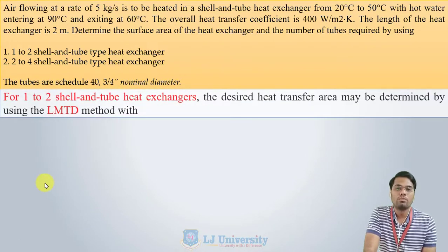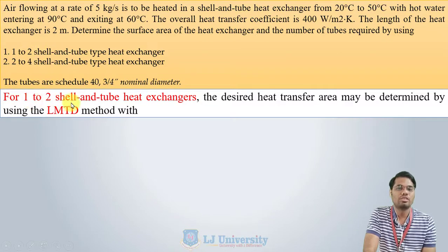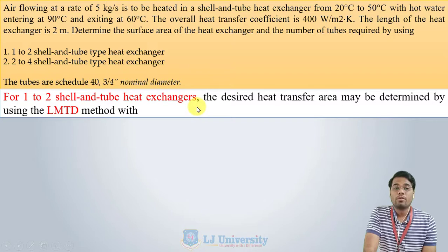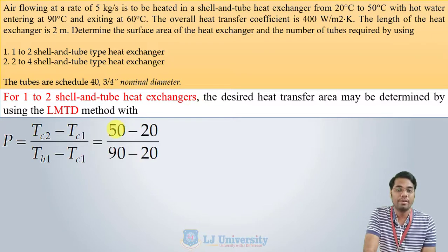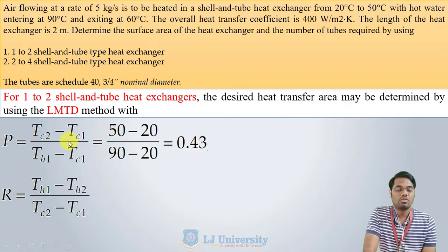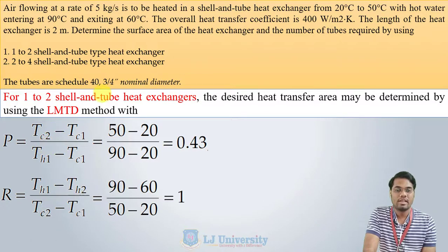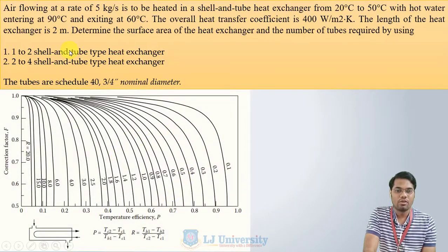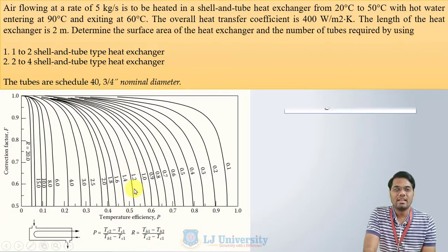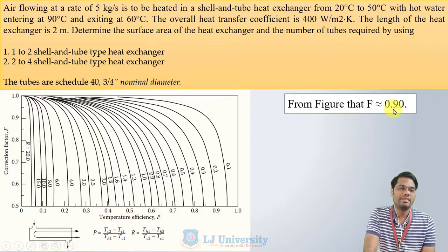For Case 1 — the 1-2 shell and tube heat exchanger — to find the required surface area A, we again need the correction factor F. Using all four temperature values, we calculate P = 0.43 and R = 1. From the appropriate graph for the 1-2 shell and tube heat exchanger, the correction factor F is approximately 0.9.